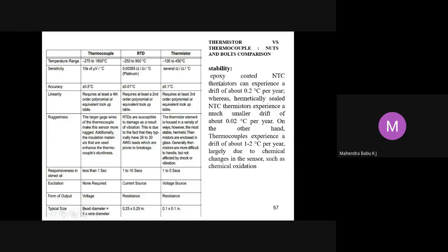And with respect to stability, an epoxy coated NTC thermistor can experience a drift of about 0.2 degrees Celsius per year, whereas a hermetically sealed NTC thermistor experiences a much smaller drift of about 0.02 degrees Celsius per year. On the other hand, thermocouples experience a drift of about 1 to 2 degrees Celsius per year, largely due to chemical changes in the sensor, such as chemical oxidation. So this is one of the important differences between a thermistor and a thermocouple.